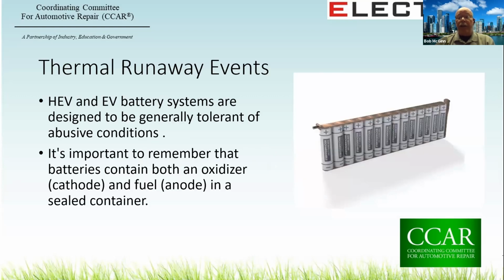So systems are designed to generally be tolerant of abusive conditions such as overcharge, short circuit, crush, fire exposure, over discharge, and mechanical shock or vibration. Propagation of a thermal runaway from cell to cell can lead to a cascading failure of the battery module that results in a fire that can be extremely difficult, if not impossible, to extinguish. And this is regardless of whether that is a prismatic cell or a string of 18650s or 21700s, which are the newer batteries.